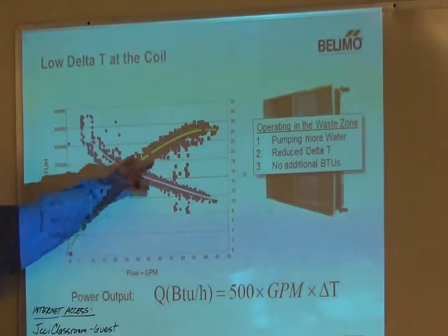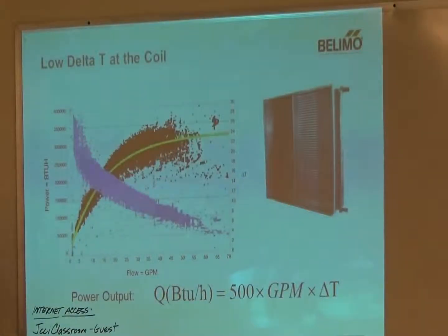You see it down here a little bit better, and we talked about these curves. I see a lot of these curves, and I don't see ones that are this pretty, ever really. Every once in a while. But this is from MIT. This was maybe a couple hour sample. We got a really good sample. It's nice to put in our brochures and show everybody. But in reality, every system's going to be different. A VAV system from a constant volume system, they're all going to react and act differently.